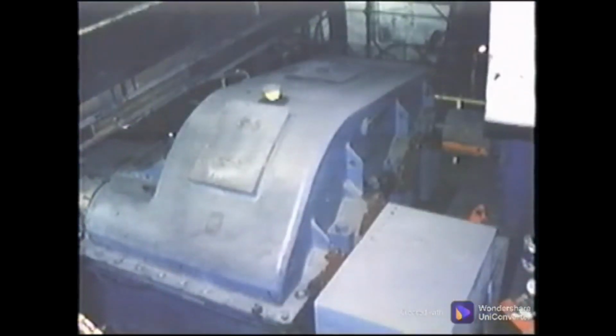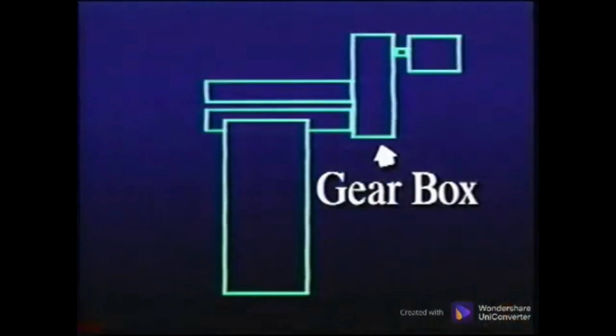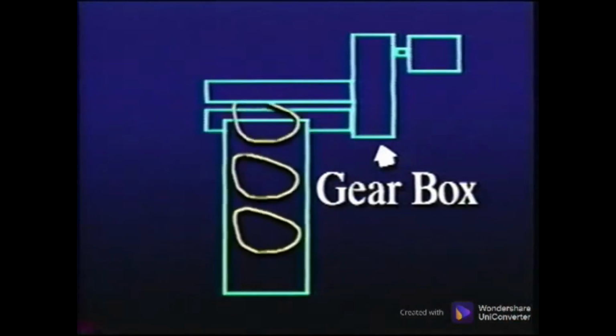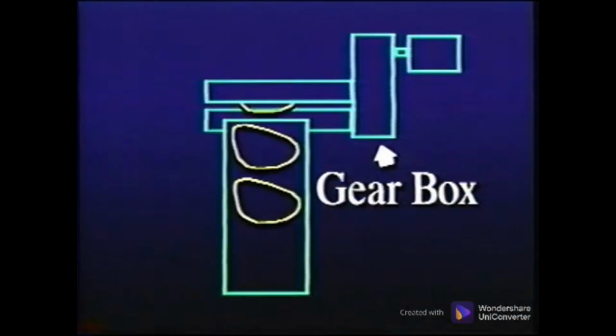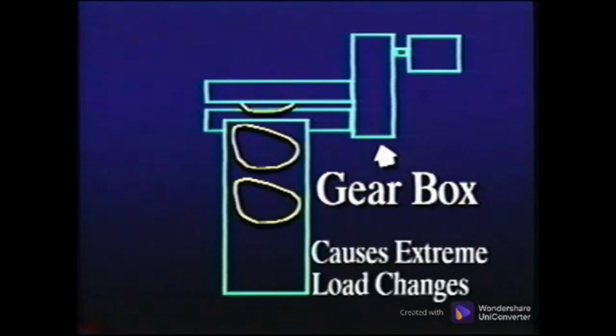The effects of load can be seen in this gearbox, which drives 2 output shafts used to mix the raw ingredients for rubber tires. The raw ingredients are placed on a conveyor in 500-pound batches. One batch is dumped in, processed, and out before the next is dumped. This means the load on the gear drive varies from one extreme to another in a matter of seconds. The data was collected and stored on a digital audio tape, so it can be played back live to view the spectrum and waveform in the analyzer.